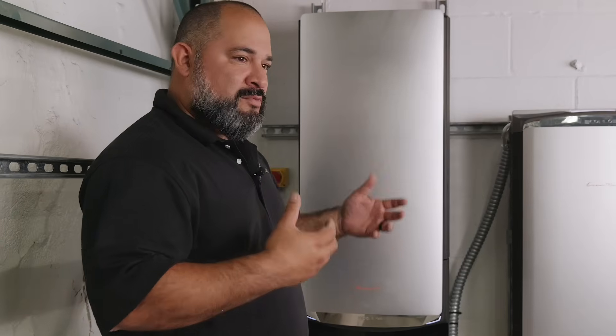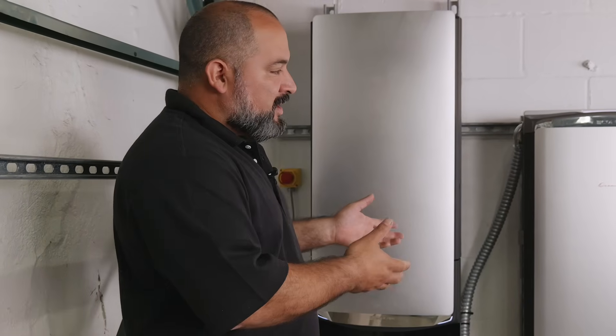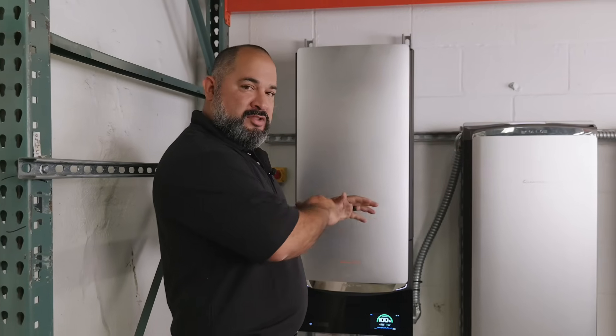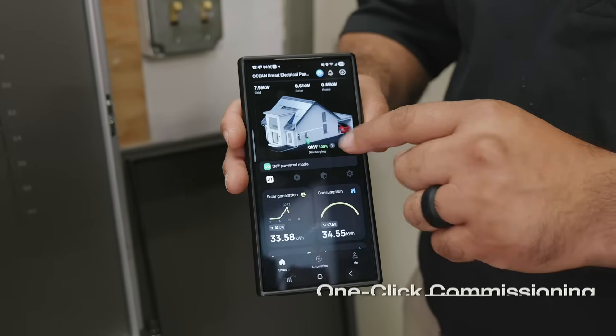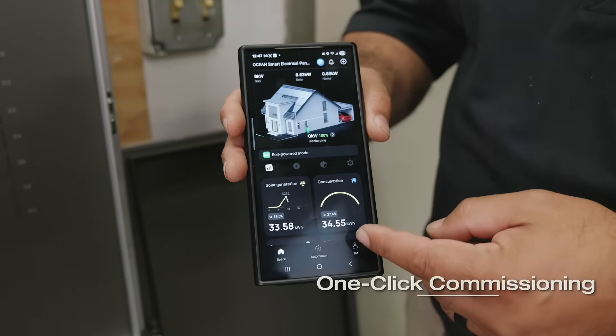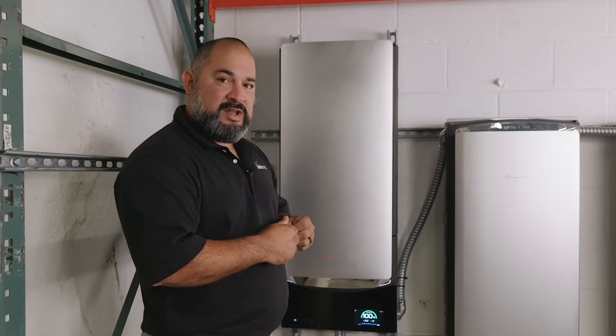Typically, installers run anywhere from four to eight hours installing the inverter or battery and trying to commission. In our case at the test lab, we were able to install two batteries and the inverter in less than two hours. The commissioning with the app took just five minutes — it discovered all devices automatically. We were very impressed with the commissioning process and how efficient it went.